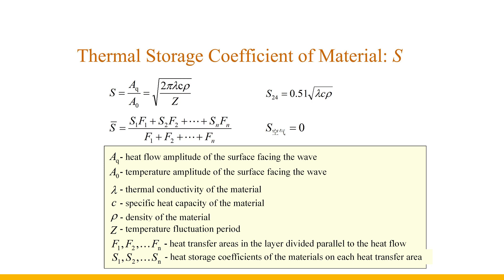S₂₄ is the heat storage coefficient with a fluctuation period of 24 hours. The average heat storage coefficient is used when a layer is composed of several materials, where F1, F2, and Fn are the heat transfer areas in the layer divided parallel to the heat flow, and S1, S2, and Sn are the heat storage coefficients of the materials on each heat transfer area. The heat storage coefficient of air is zero.